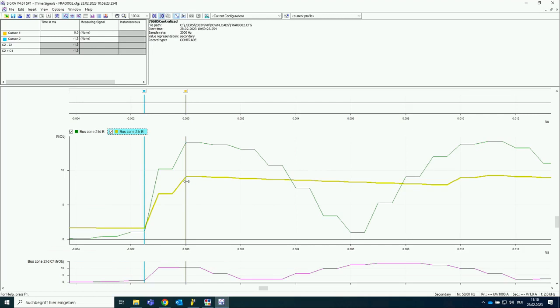And this is even multiplied with the stabilization factor. So that means that's really a jump higher than 10 times the nominal current. And at the same moment, we are in the tripping area. That means from the very beginning, the differential current is above the restraint current multiplied with the stabilization factor. So that's really a clear indication this will for sure trigger a 1 out of 1 trip by the busbar protection. And from the fault inception, that's here at the blue line, around the fault inception.